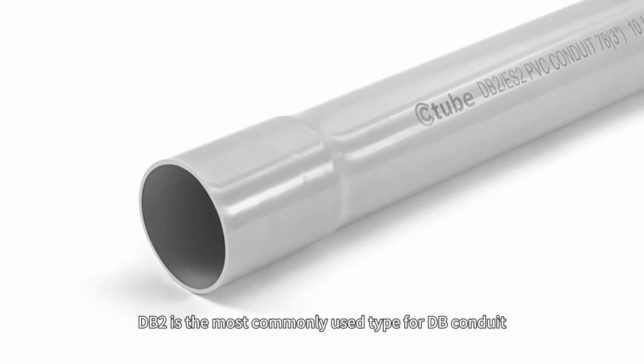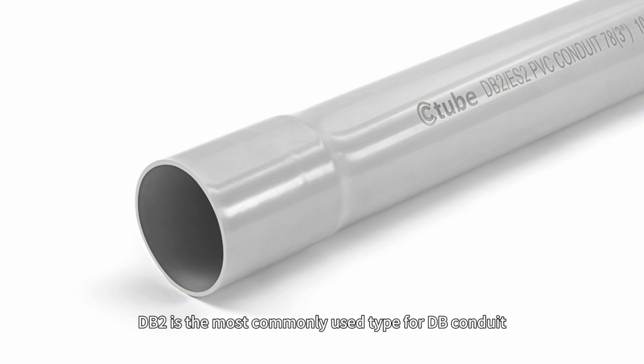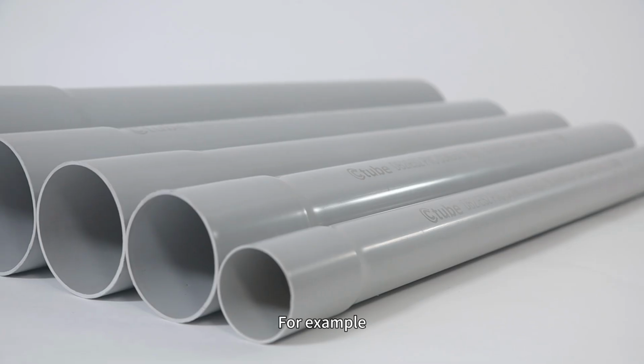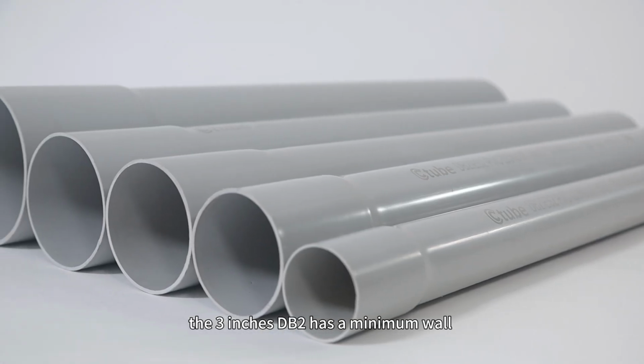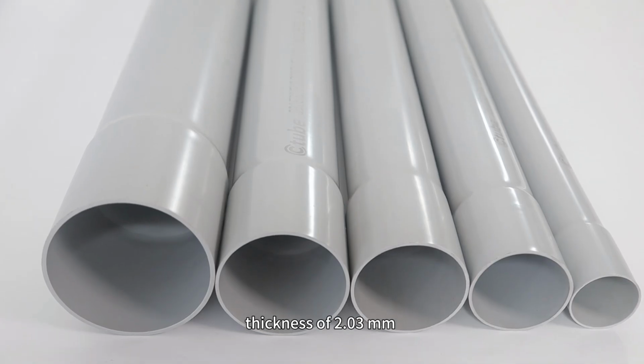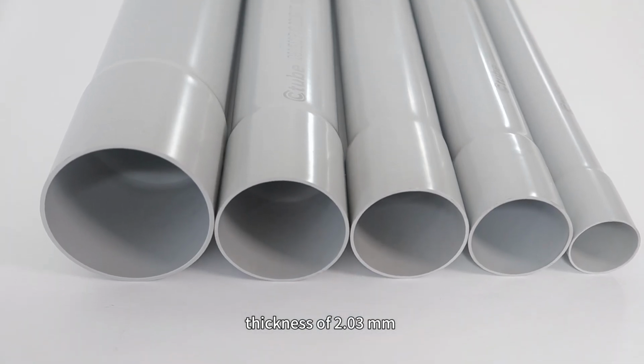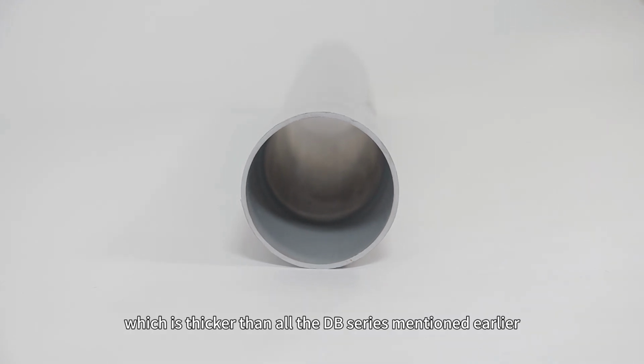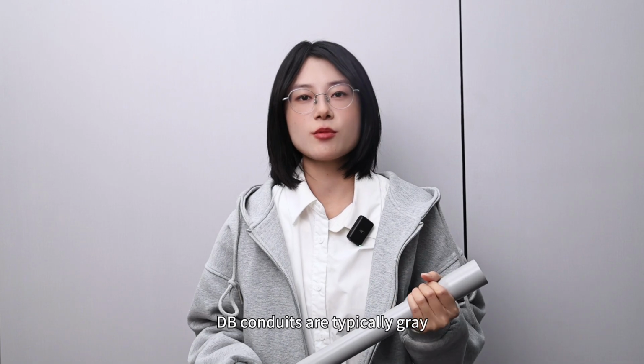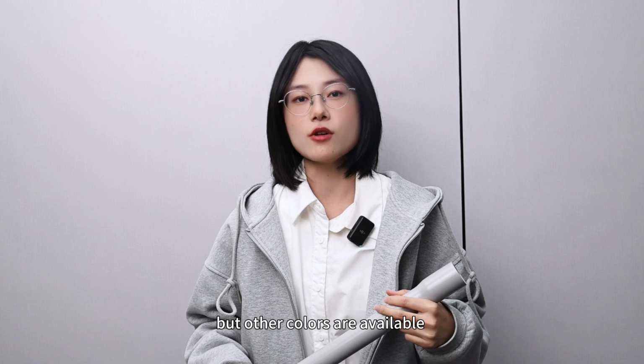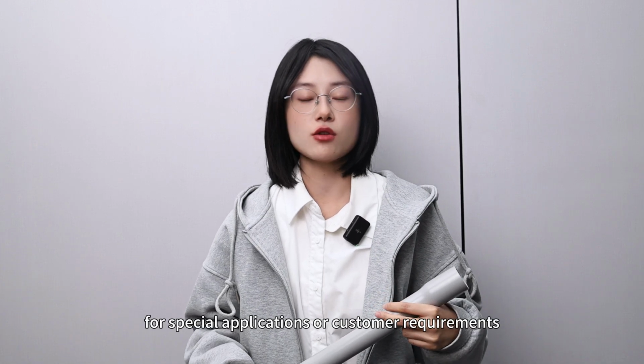In Canada, DB2 is the most commonly used type for DB conduit. For example, the 3 inch DB2 has a minimum wall thickness of 2.03 mm, which is thicker than all the DB series mentioned earlier. DB conduits are typically gray, but other colors are available for special application or customer requirements.